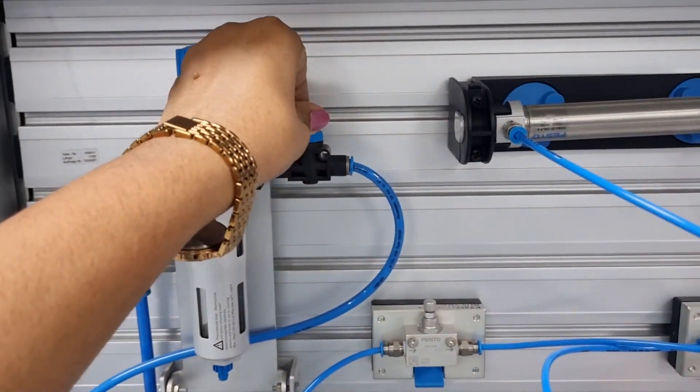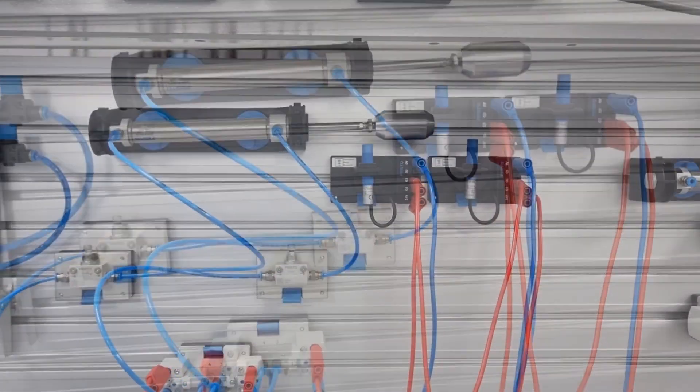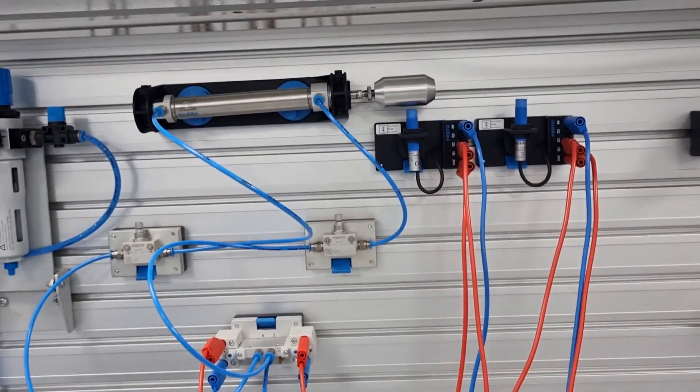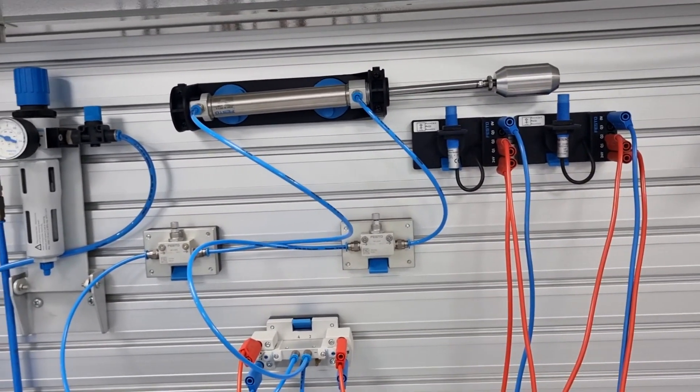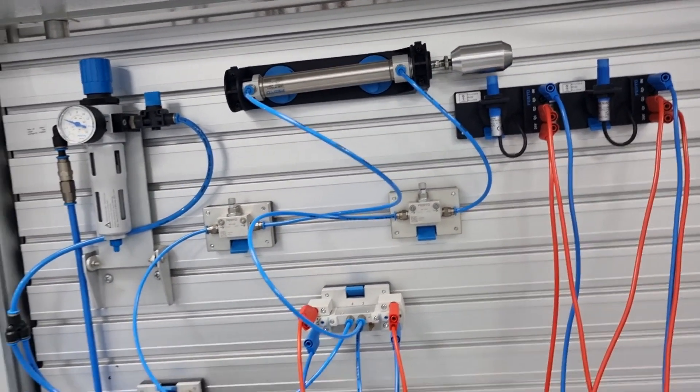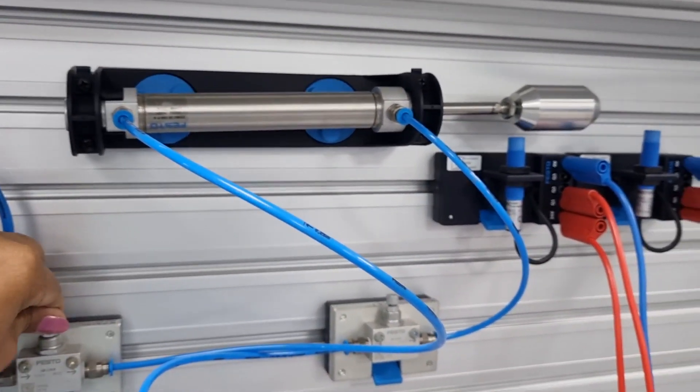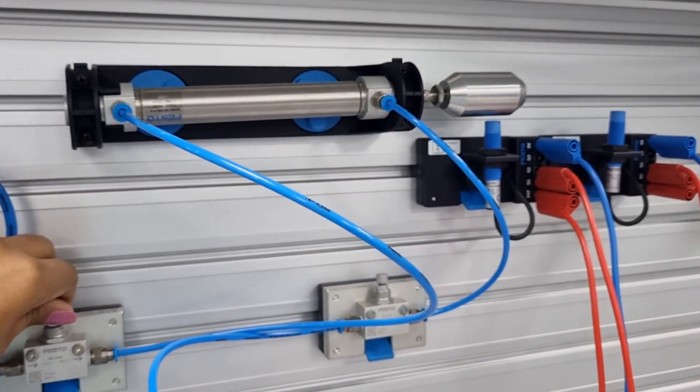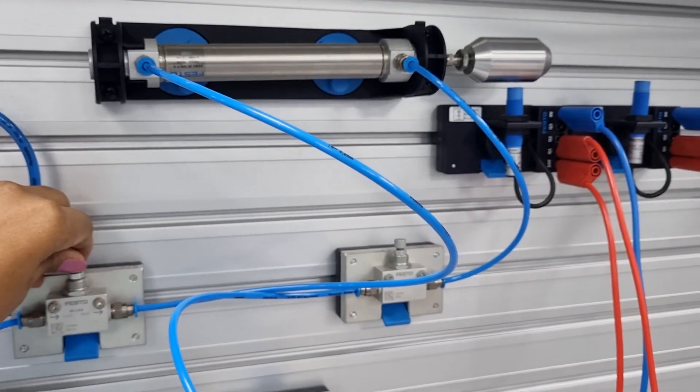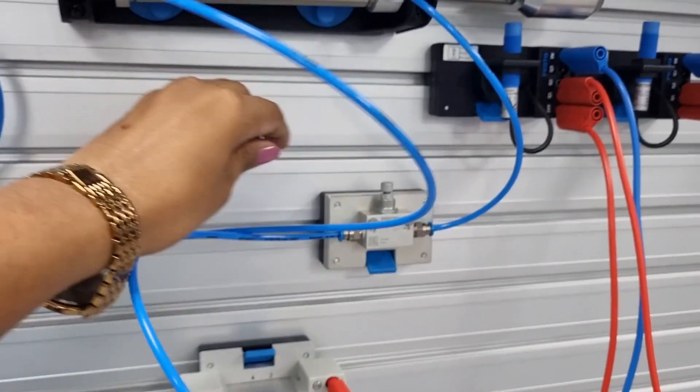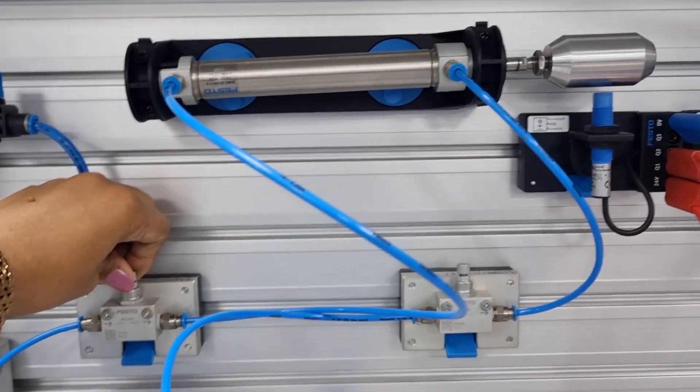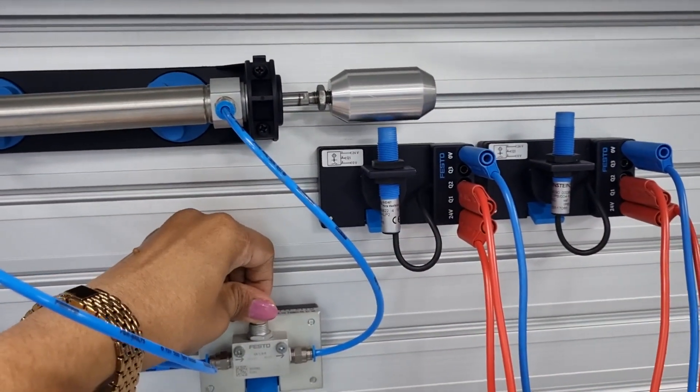You can see the continuous movement of this double acting cylinder. Now it is working fine. The movement is very slow because I have adjusted the flow control valve. If I change this, you can see the extension speed is increased. Now I am adjusting the retraction speed. You can see the retraction speed has increased.